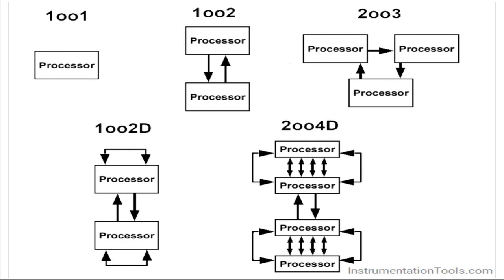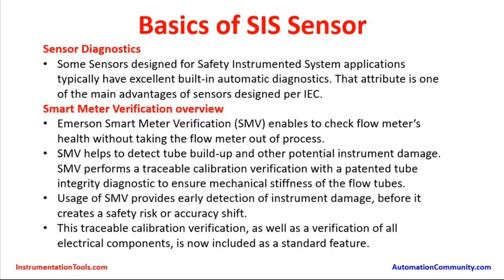In some cases it could be two-out-of-two, or one-out-of-one. These voting configurations depend entirely on the process requirement, decided by process safety experts and safety design experts during the design of the process. Sensor diagnostics is another important requirement to ensure that SIS sensors are working reliably and accurately. Sensors designed for SIS applications typically have built-in automatic diagnostics, which is one of the main advantages of sensors designed per IEC standards. IEC standards mandate self-diagnostics for SIS sensors.